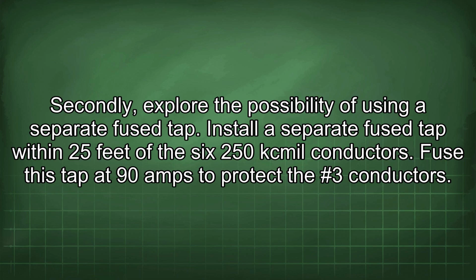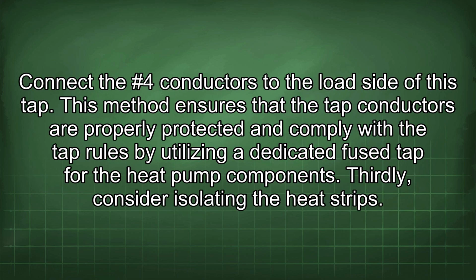Secondly, explore the possibility of using a separate fuse tap. Install a separate fuse tap within 25 feet of the 6 250 kcmil conductors. Fuse this tap at 90 amps to protect the #3 conductors. Connect the #4 conductors to the load side of this tap. This method ensures that the tap conductors are properly protected and comply with the tap rules by utilizing a dedicated fuse tap for the heat pump components.